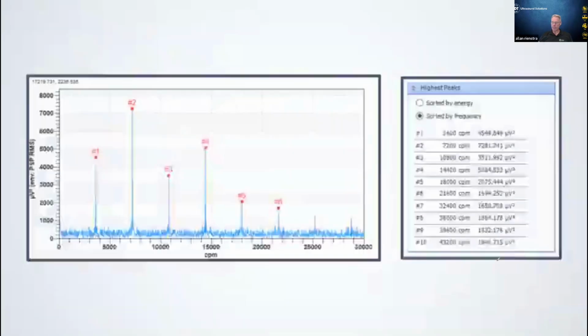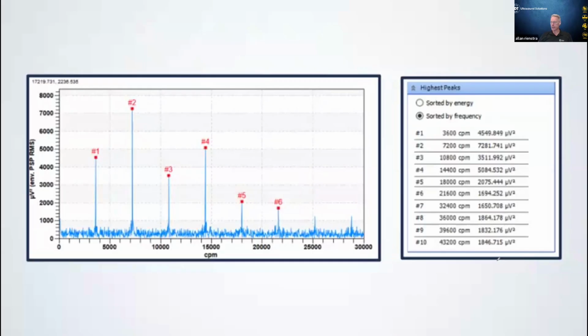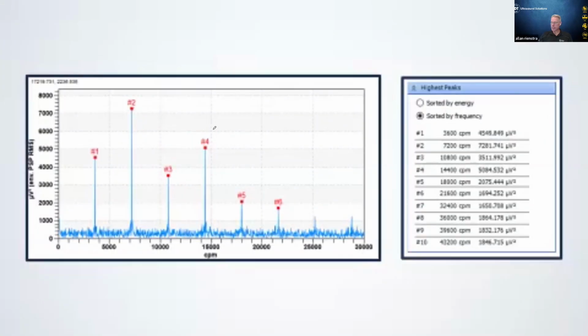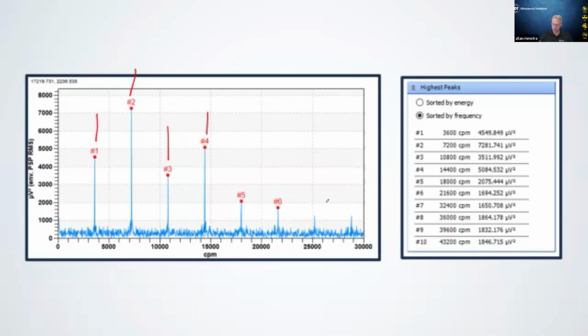And then we were able to take that time waveform and bring it into the spectrum to determine, again, these consistent peaks tell us that it is corona discharge. It's not an arcing situation or a tracking situation.